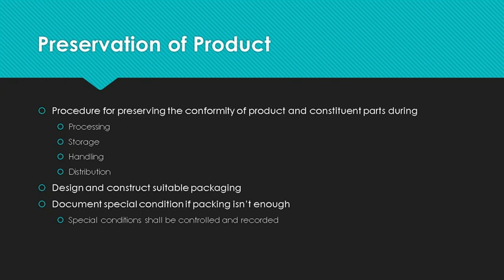Conformity of product does not end with final inspection and testing. All product and parts must be protected against damage during production, while in storage, while being moved, and during shipping. Your organization is responsible to design and construct suitable packaging — don't leave it to the shipping clerk to decide which box to use or how much stuffing to put around the product. If the product needs special conditions such as anti-static barriers or temperature controls, your organization must document how conditions will be controlled and record that those controls were implemented.